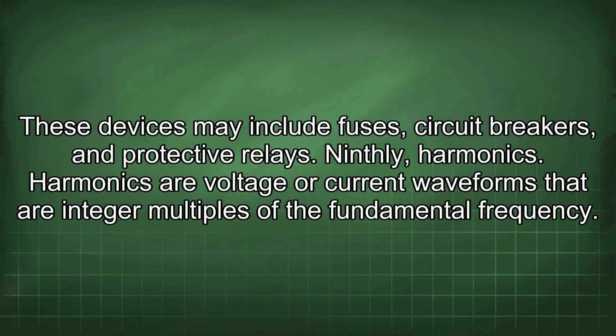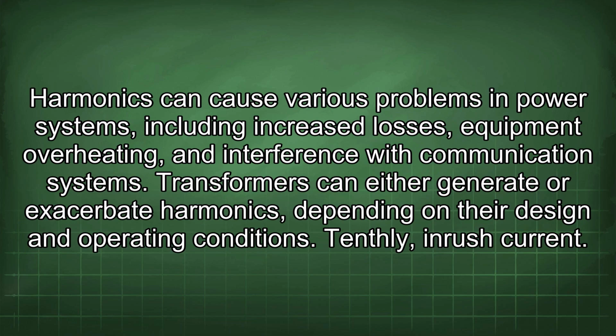Ninthly, harmonics. Harmonics are voltage or current waveforms that are integer multiples of the fundamental frequency. Harmonics can cause various problems in power systems, including increased losses, equipment overheating, and interference with communication systems. Transformers can either generate or exacerbate harmonics, depending on their design and operating conditions.